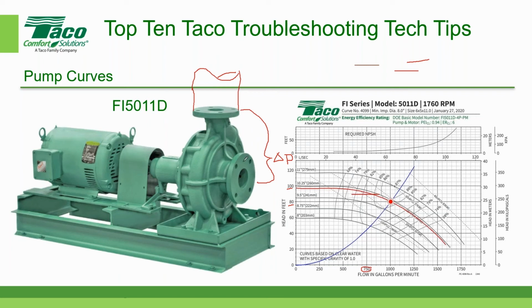And what we have to make sure is that we correct for the velocity. In this case, the outlet of the pump is smaller than the inlet, and so the outlet velocity is going to be greater than the inlet, and so we have to make that correction. So if we take the data at the outlet velocity, then we have to correct that outlet velocity for the delta P, so we get the accurate delta P. So let's assume that they did that correctly, and they gave us the corrected value, and it was 92 feet. Well, at 92 feet, which we said was roughly here on the curve, that's 92 feet.